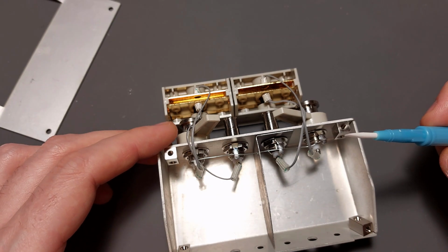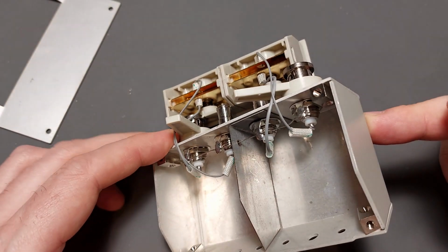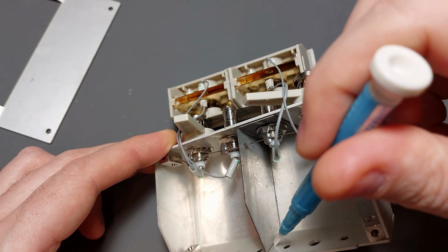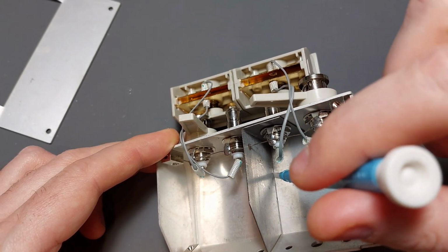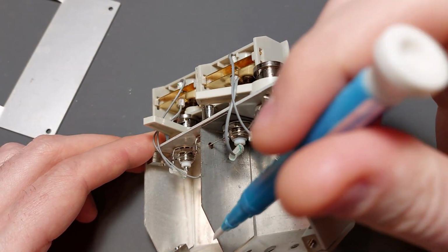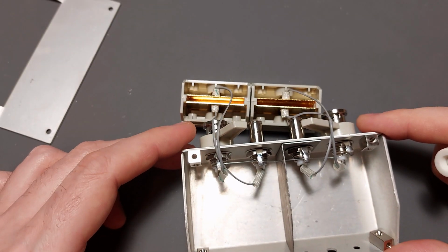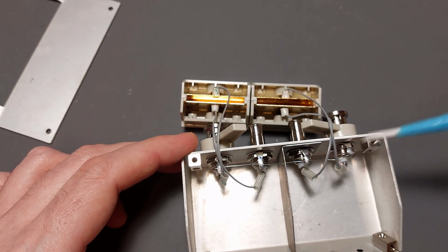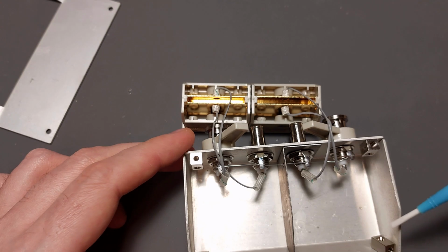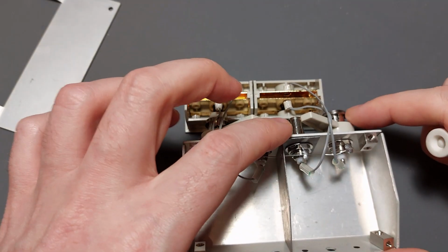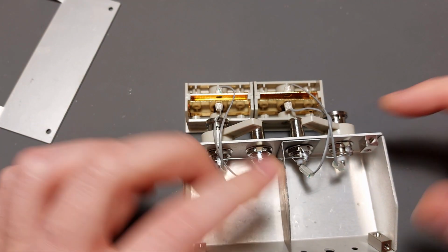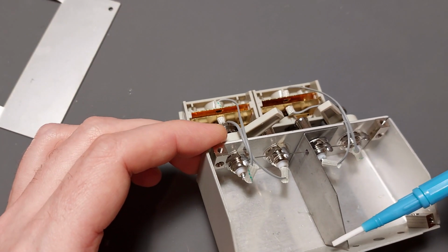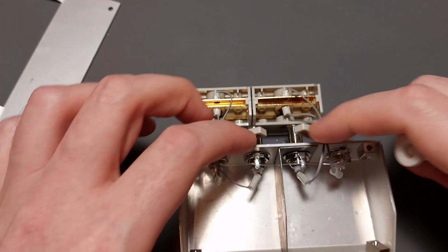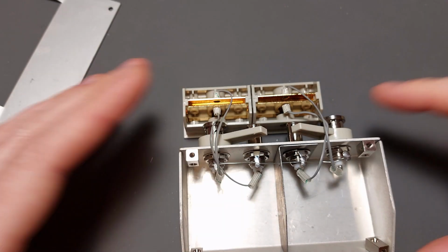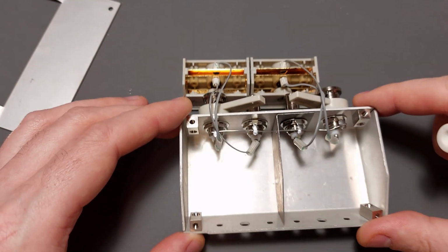Let's go to the disadvantages. So the first thing that I see is this huge gap in the shield. There's quite a large gap, and this is not a good thing, because this one should be completely isolated. And you cannot bend it or make this gap smaller, because there is no way for this chassis to bend even more.